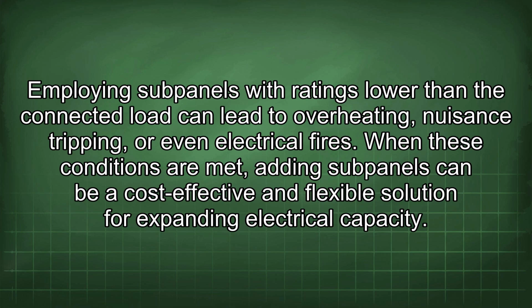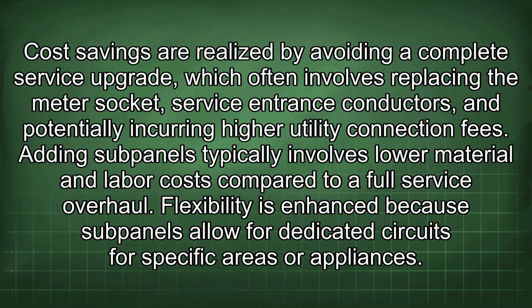When these conditions are met, adding subpanels can be a cost-effective and flexible solution for expanding electrical capacity. Cost savings are realized by avoiding a complete service upgrade, which often involves replacing the meter socket, service entrance conductors, and potentially incurring higher utility connection fees.